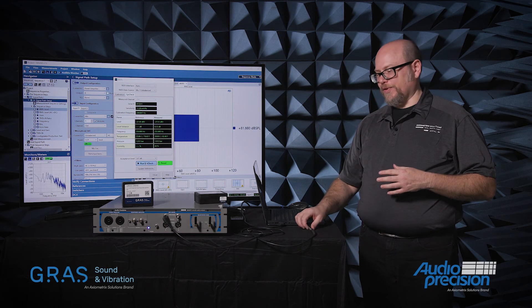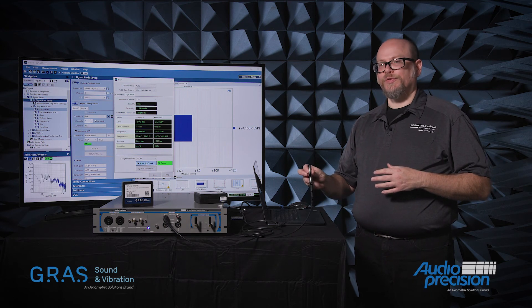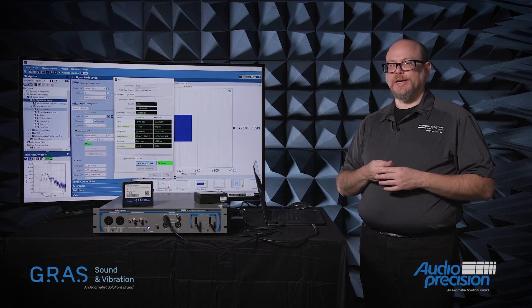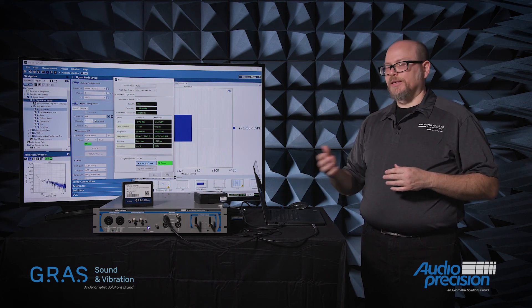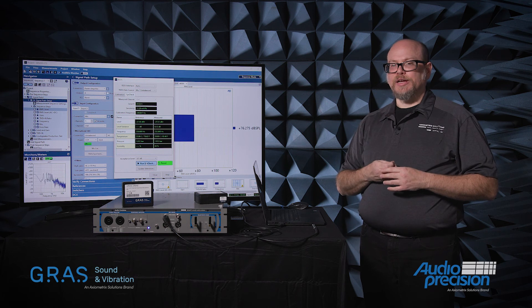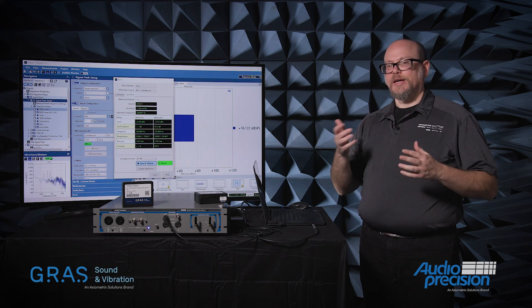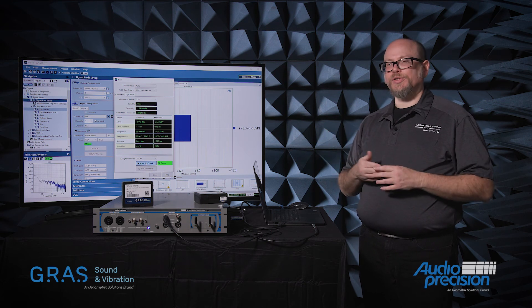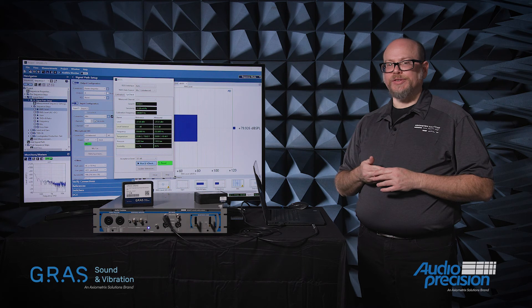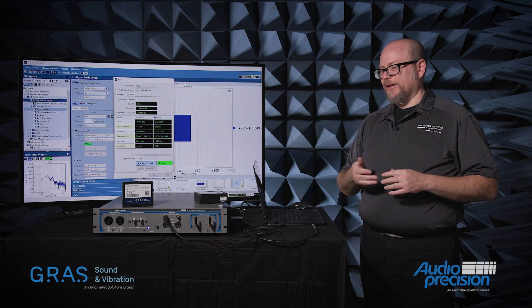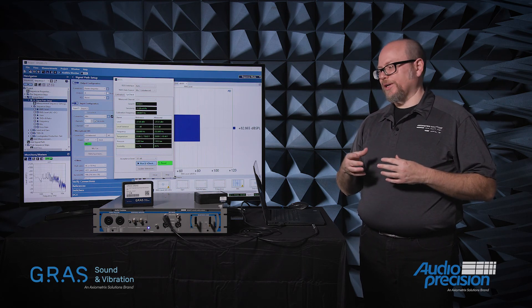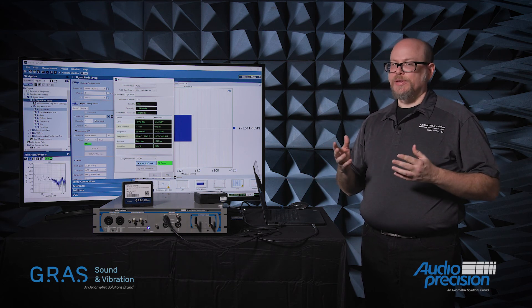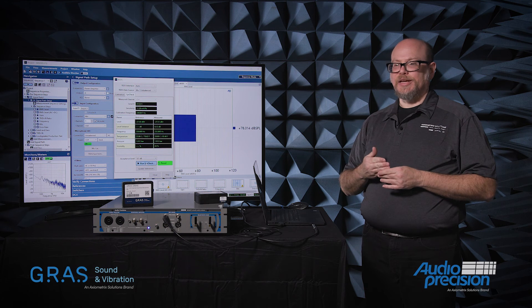I've not only verified the sensitivity of the microphone, but explicitly I've also verified the cable between the microphone and the analyzer, and even the analyzer itself — by measuring that reference voltage, I've verified it as well. So I can now have 100% confidence that my analysis system is working correctly. I have all the benefits of doing a manual calibration with an acoustic calibrator, but without having to physically touch anything.